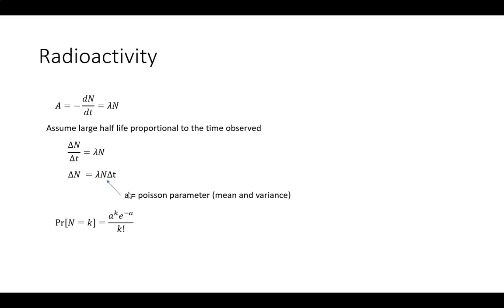So that's where they calculate what we need. You use the I for the detector to match, and then we calculate the number of decays from here. And from this we can figure out what lambda will be needed. So for instance, we might say, hey, I need a total of 7 million photon hits or something to get a good image. We calculate what we want. And then we'll take that intensity equation plus this, and we can calculate what our I or what our lambda has to be to meet that I requirement, given I want to do like a 10-minute time period or something.